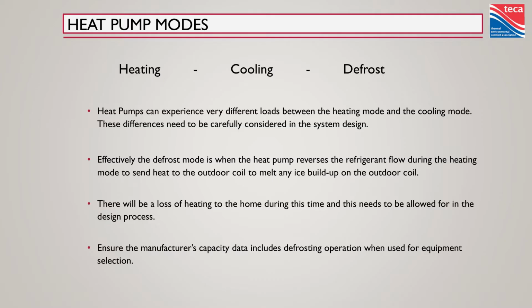We heat, we cool, and we defrost with an air source heat pump. So we talk about heating water, chilling water, but anytime we're heating with air as a source, we're going to start freezing up that water on the coil. So the heat pump's going to go into a defrost mode, and it's going to melt off all of that ice and frost on that coil so it can go back to heating mode. If we don't do that, that big block of ice can't transfer heat properly, the fans can't blow air across it anymore. So it's very similar to air conditioning cycle, but the fans stop.